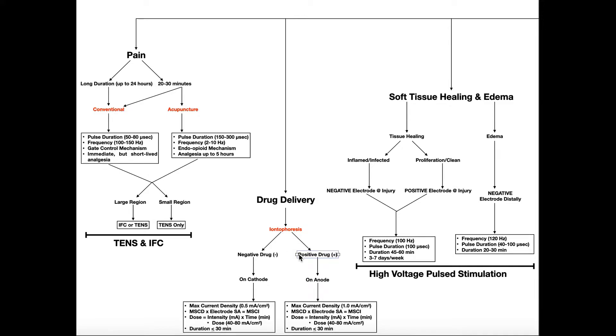If we have a positively charged drug, we want to put it on the anode, which is the positively charged electrode, so it will repel positive charges and cause this drug to migrate towards the negative electrode, or the cathode. Once we have this appropriate setup, we need to select our parameters, and the parameters depend on whether or not the drug is on the cathode or on the anode. Remember that the cathode has a maximum safe current density, or MSCD, of 0.5 milliamps per square centimeter, whereas the anode has a maximum safe current density of 1.0 milliamps per square centimeter. To review some of this math, go take a look at the iontophoresis video.